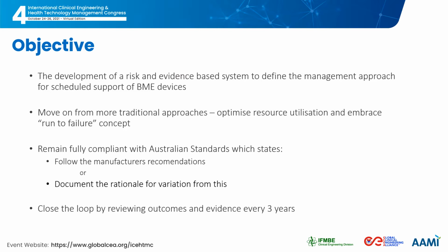The need, of course, was to remain fully compliant with Australian standards, particularly Australian Standard 3551 that I mentioned in my previous slide, and that has some very clear recommendations, and it includes, as a default position, follow the manufacturer's recommendations for scheduling routine service, or, and this is the clause that we were using, document the rationale for any variation from manufacturer's recommendations. That left the door clearly open to take a smart, science-based approach to our activities.